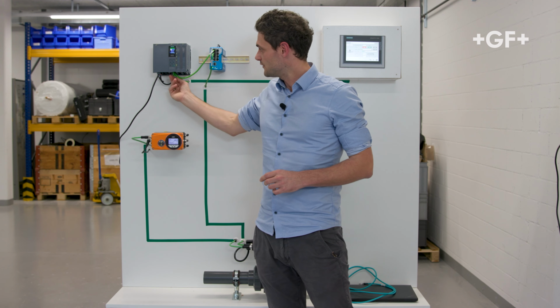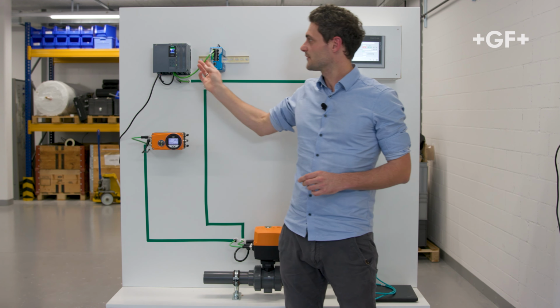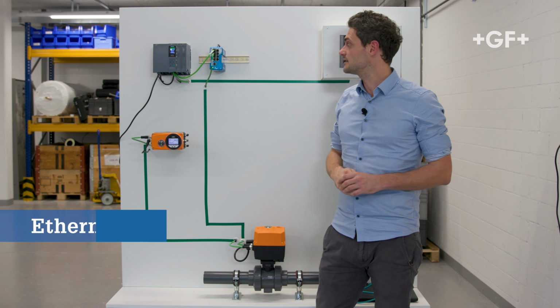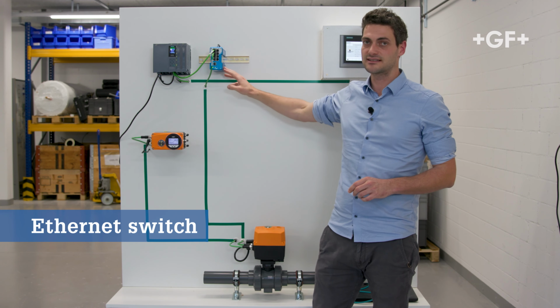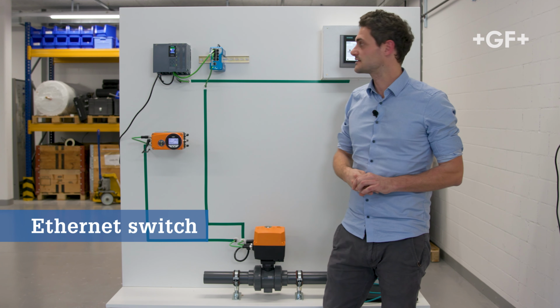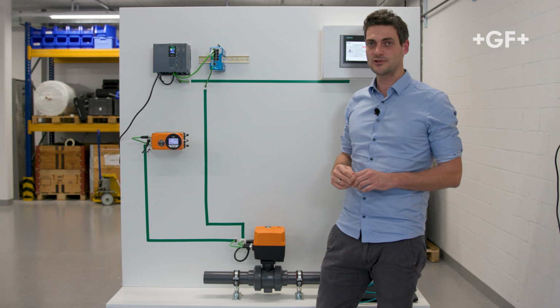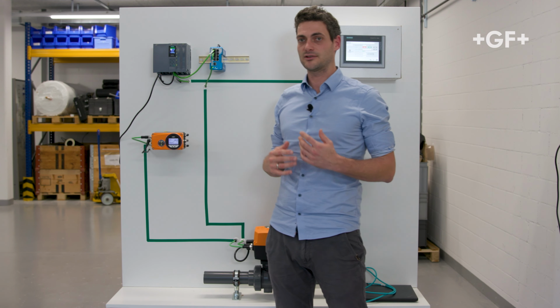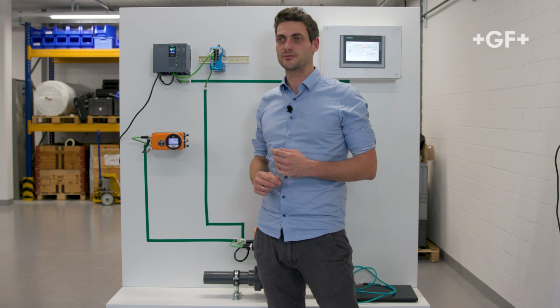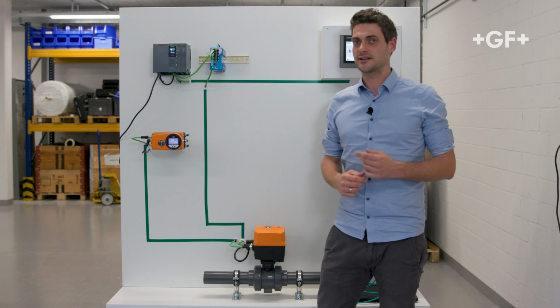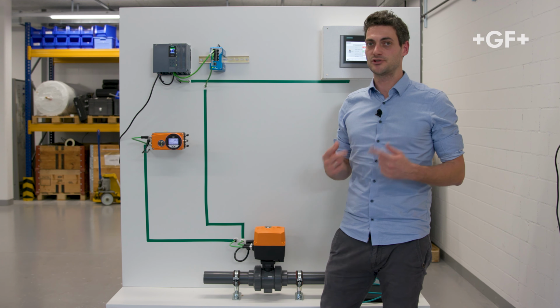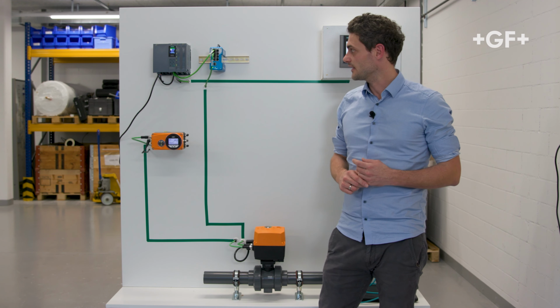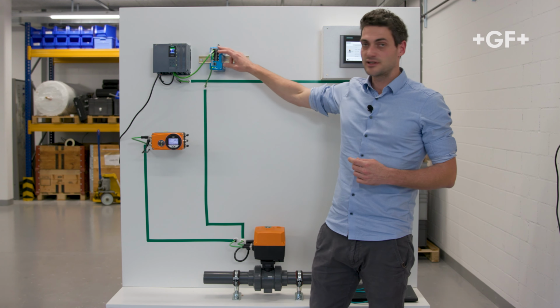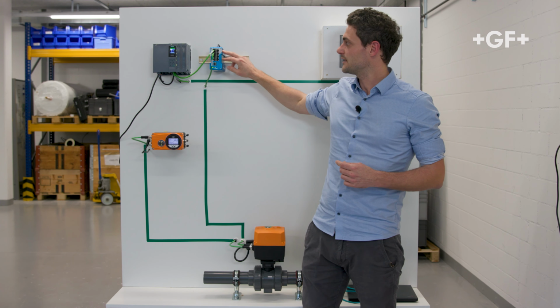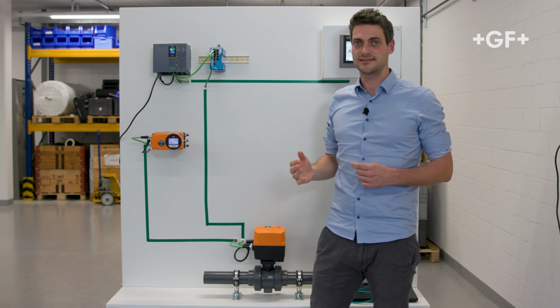We can go directly with one Ethernet cable to the first Ethernet component. In this example, it's an Ethernet switch, in this example of the company Indusol. It's a great device and it offers a lot of functionalities in terms of cybersecurity, redundancy, and especially for troubleshooting the Profinet network.